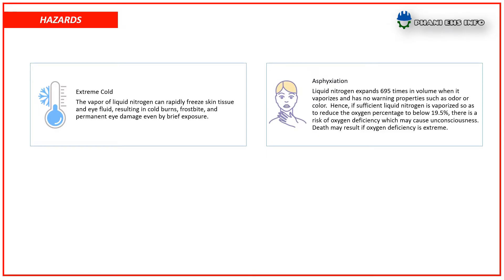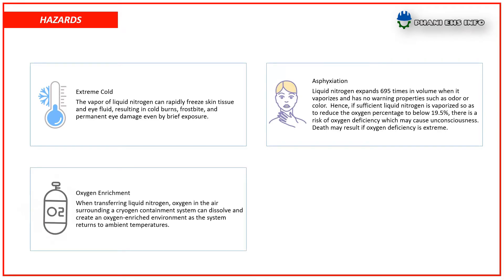Asphyxiation — liquid nitrogen expands 695 times in volume when it vaporizes and has no warning properties such as odor or color. If sufficient liquid nitrogen is vaporized so as to reduce the oxygen percentage below 19.5%, there is a risk of oxygen deficiency which may cause unconsciousness. Death may result if oxygen deficiency is extreme.